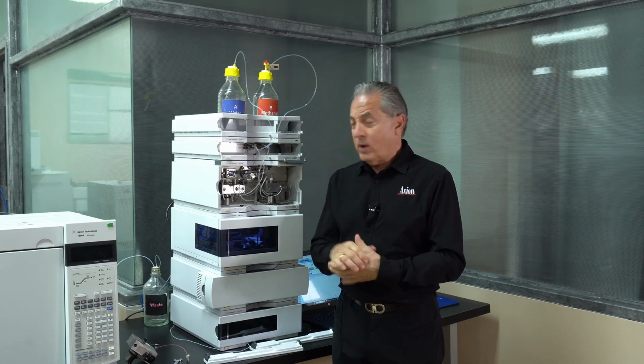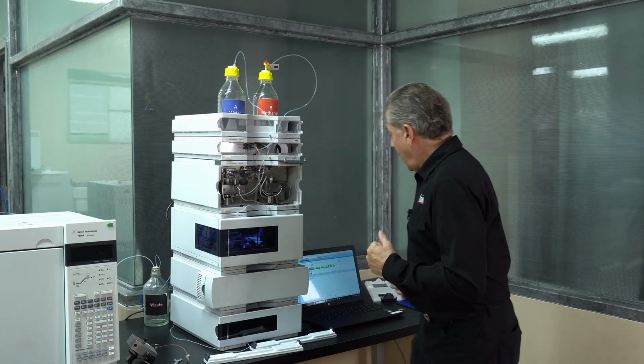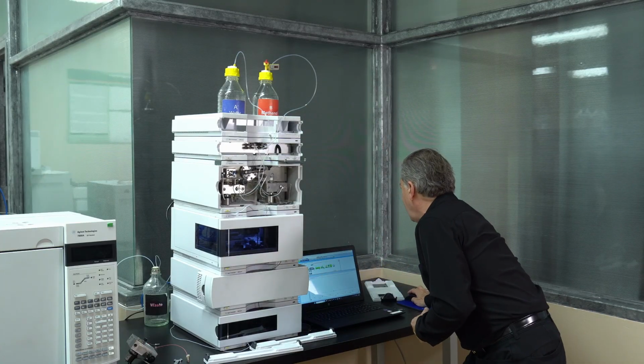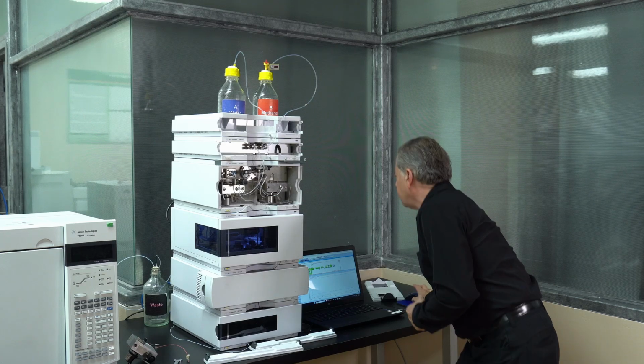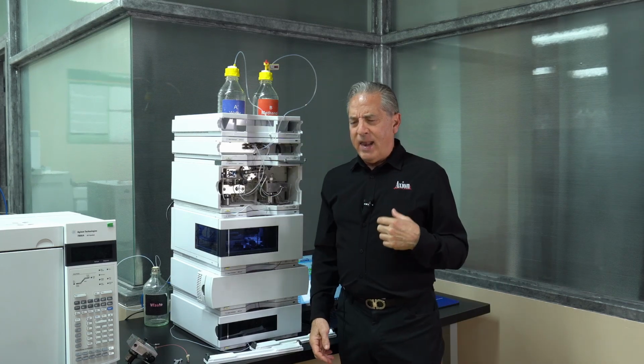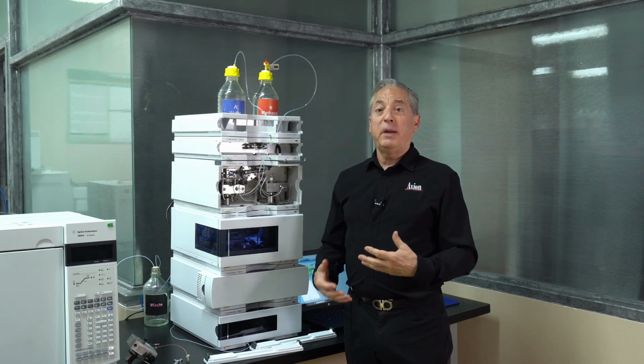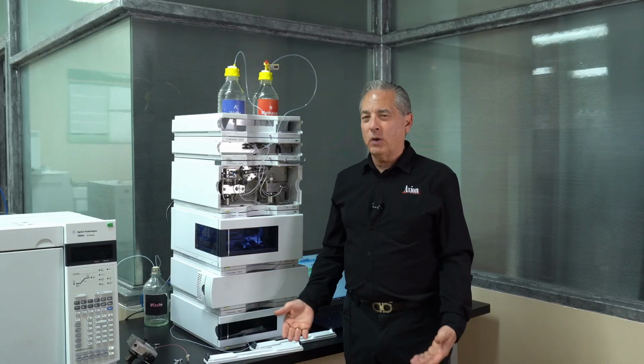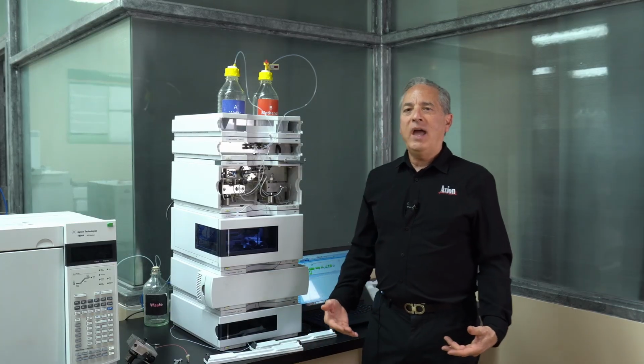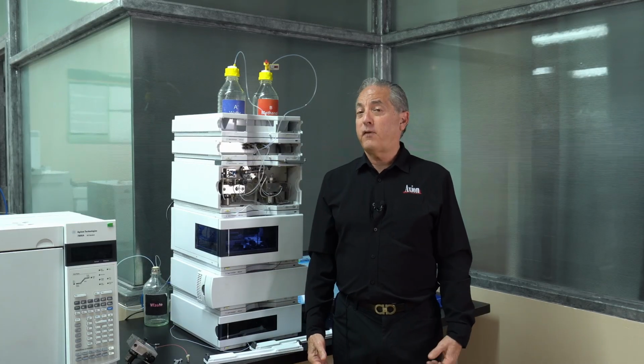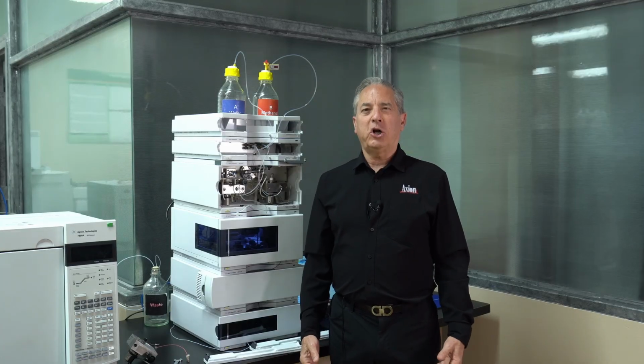As we talk about the instrument, I'm going to go ahead and turn it on. By doing this, we'll hear the pump start up, and as it starts up, it's going to start generating a pressure curve where we could actually look at the pressure. When an HPLC pump has a problem, the first thing we'll usually notice is a pressure fluctuation.